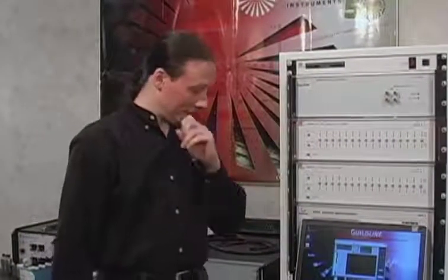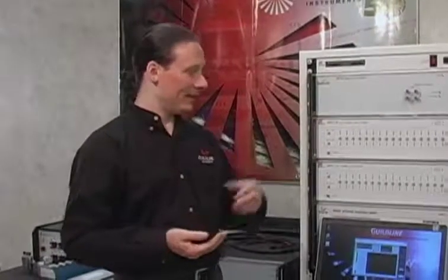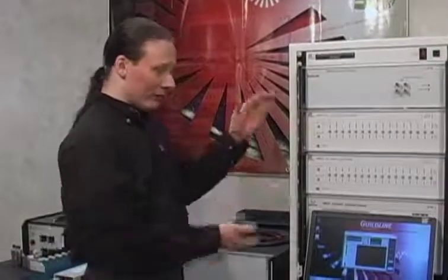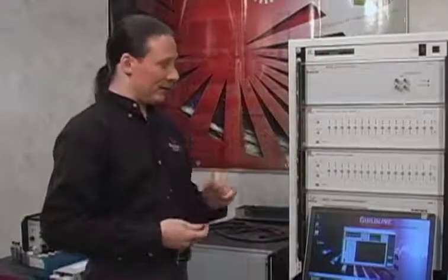The software essentially has many different file types within it, so we're going to be going through things such as resistor profile files, which are definitions of your resistors. We'll be going through some test sequence files. They basically allow you to establish batches of tests, and especially if you run very common routine tests in your lab, then you can set these profiles for tests, and they'll go ahead and run that sequence, and you can recall it and rerun the sequence over and over again, especially if it's a standard practice.